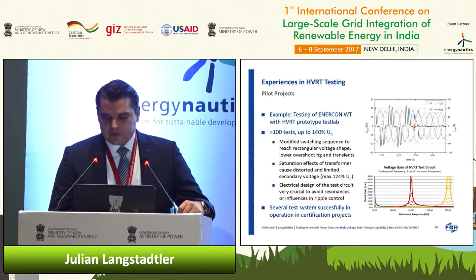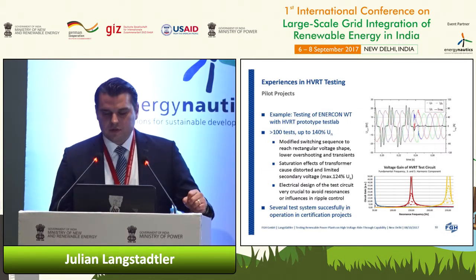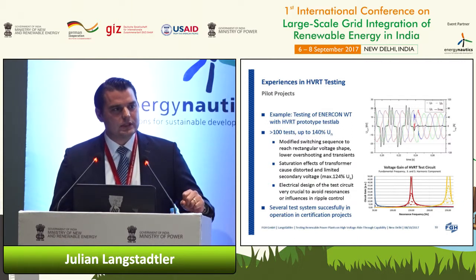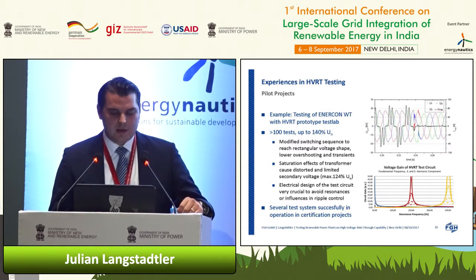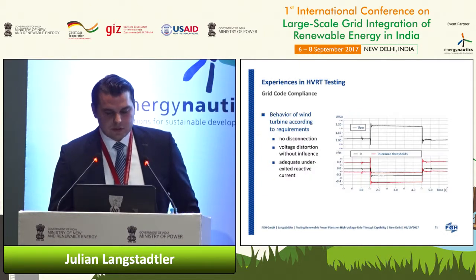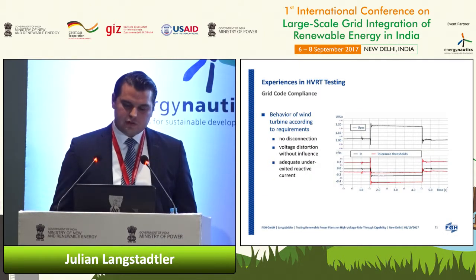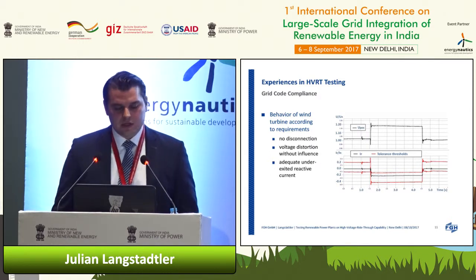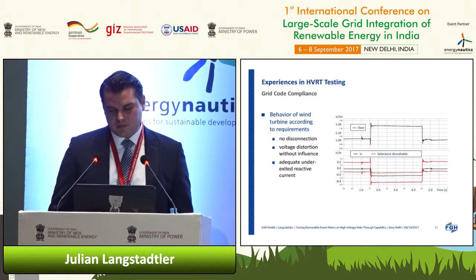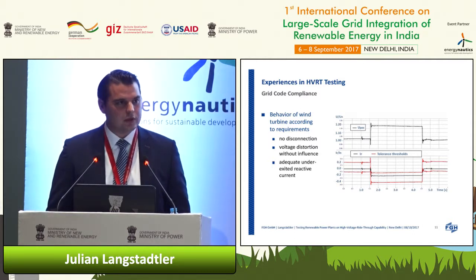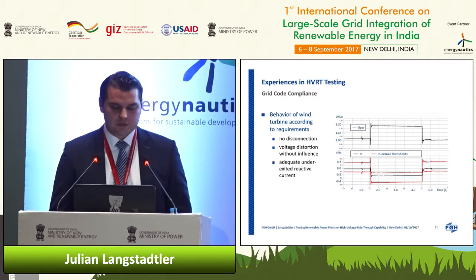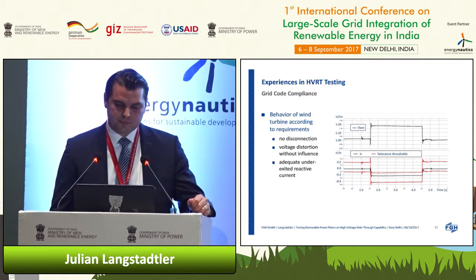As you can also see in the lower right picture, it's very important to have a damping resistance within the circuit itself, because otherwise you have amplification of harmonics or even interference with the ripple control, so that must be nicely harmonized. You can also see, because of the requirement that was introduced in Germany to inject a reactive current, that this specific wind turbine from the pilot testing also replied to the voltage swell with an appropriate reactive current injection, within the tolerances of the German grid code.